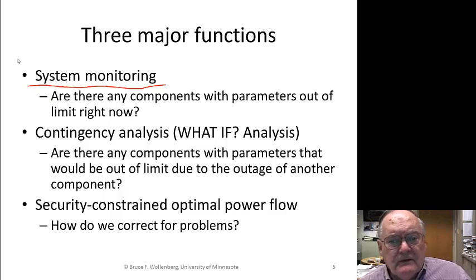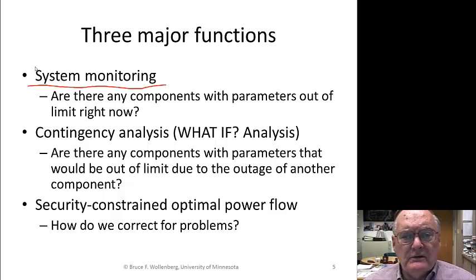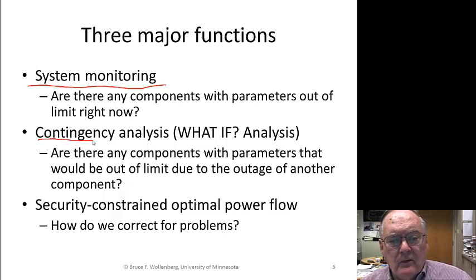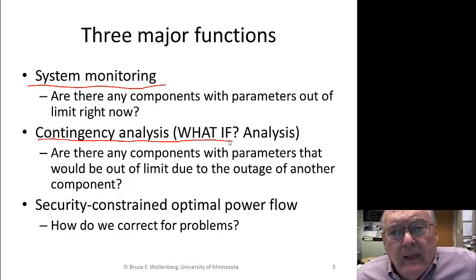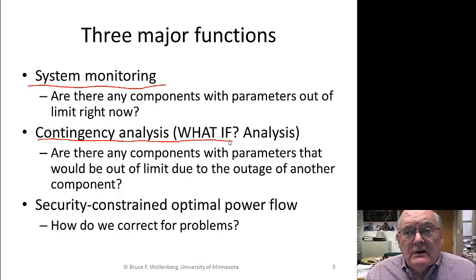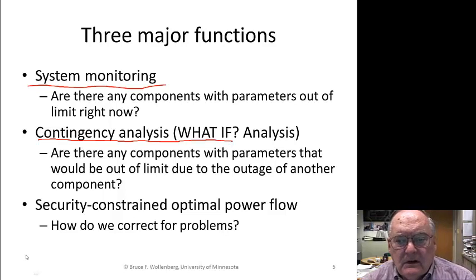So if the system is not experiencing any alarms, meaning there's nothing overloaded, no voltage is too low, well, the next thing is we want to know, well, what if I have an outage, and that's going to give me an alarm. So the what-if analysis says, are there any of those components that would be out of limit due to the outage of another component? So this is the what-if. What if a generator goes out? What if a transmission line goes out? What if? And we have to test all the components for possible outages. Okay, called contingency analysis. That's the more formal term, but I like the what-if analysis.